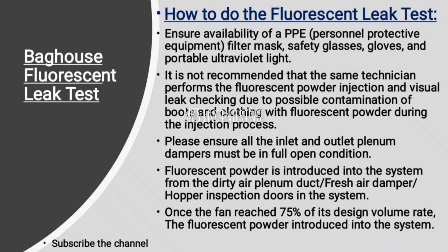Next step: ensure availability of PPE — personnel protective equipment including filter mask, safety glasses, gloves, and portable ultraviolet light. Next step: it is not recommended that the same technician performs the fluorescent powder injection and visual leak checking, due to possible contamination of boots and clothing with fluorescent powder. Next step: ensure all inlet and outlet plenum dampers are in full open condition. Next step: fluorescent powder is introduced into the system from the dirty air plenum duct, fresh air damper, or hopper inspection doors. Once the fan has reached 75% of its design volume rate, the fluorescent powder is introduced into the system.